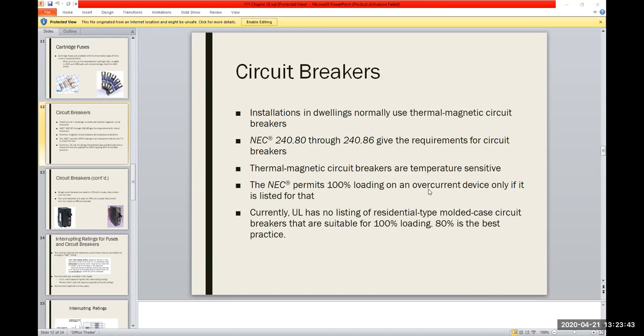So the NEC permits 100% loading on an overcurrent device only if it's listed. So you would actually have to check and make sure that you are matched. Because if it's not listed correctly for that, you could literally be using something where the load would be up at 100%, but it wouldn't trip the circuit breaker properly, in which case next thing you know, you have a fire, and that's the way that goes. And we don't want that. So you have to make sure that you're properly protected for your feeder lines, your branch circuits, if you will.